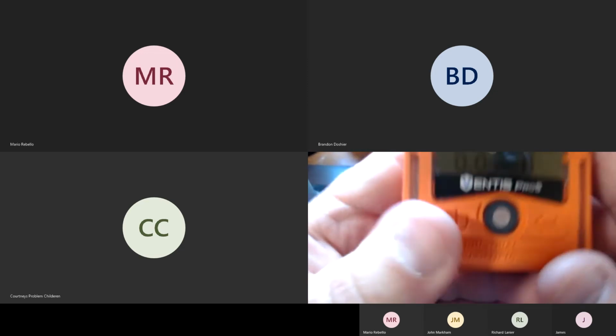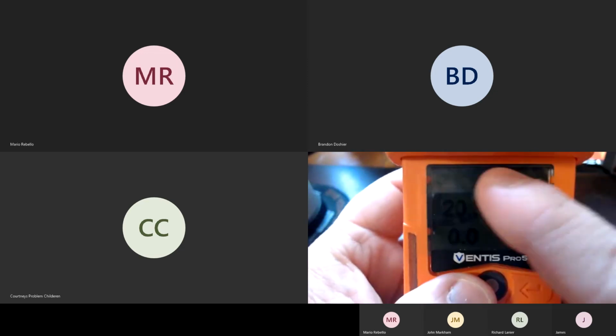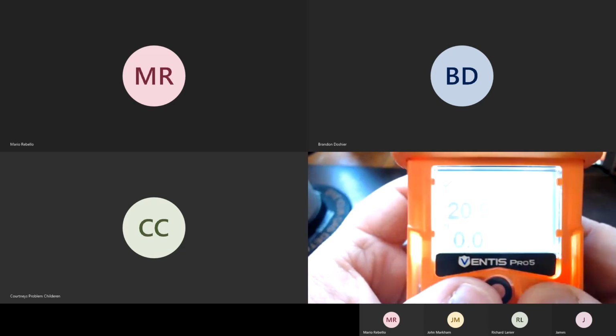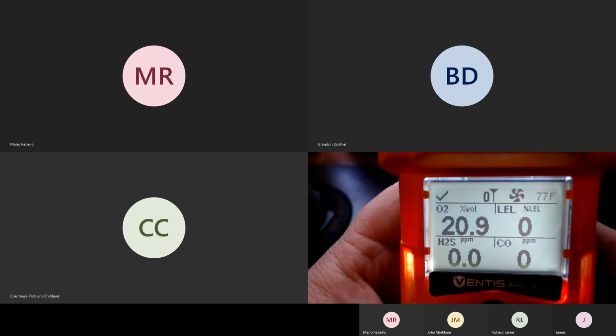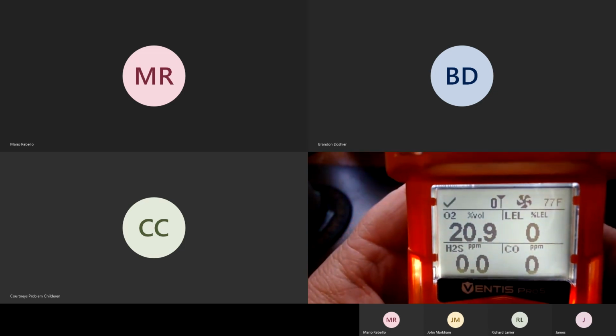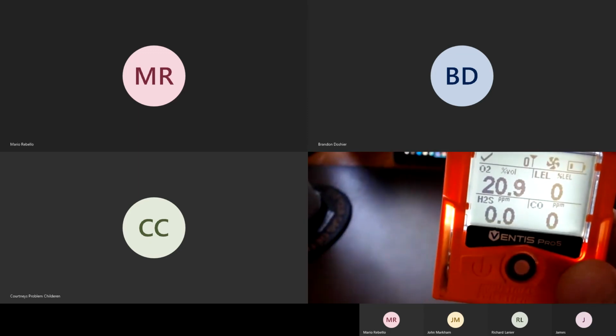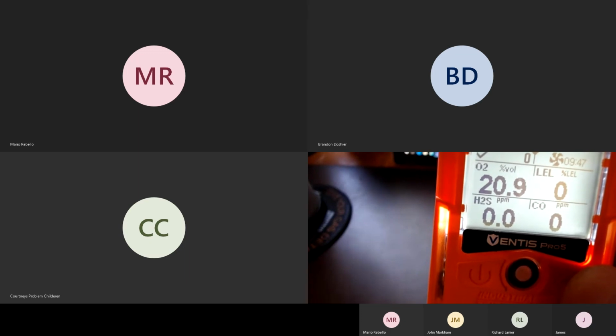Now, if it's set up in the default settings, what you're going to see next on there is it will actually come up with a little bottle on the screen with a C in it, and that's because it's looking for calibration gas. If you hit the enter button, that will allow you to calibrate the unit manually. And I'll show you here in a second how you can disable that in the settings of the instrument online.